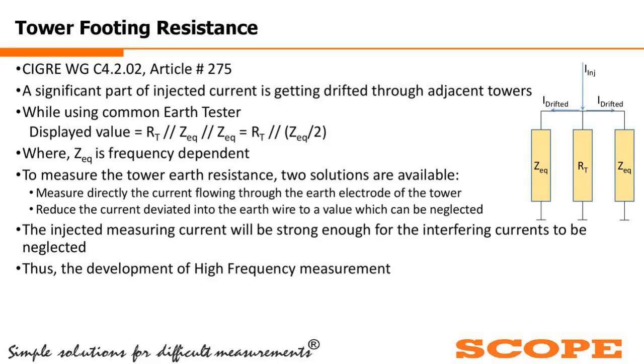Now let us have a reference of the CIGRE Working Group C4.2.02, article number 275, where it has beautifully explained the entire problem, and it is a very good paper to read. A significant part of the injected current is getting drifted through the two adjacent towers, as explained in the earlier slide, and I have kept the same equivalent circuit picture on the right hand side for reference. While using the common earth tester, whatever value is displayed on the meter will not be the value of the tower, meaning RT, my desired resistance of the tower footing. I will not be getting that value as a standard.